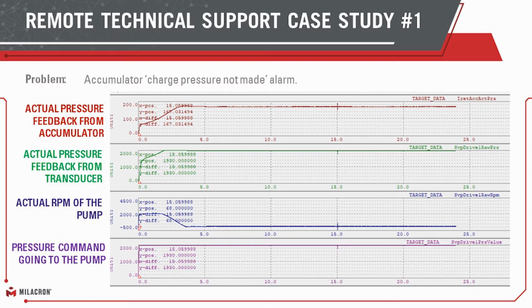Here you see an example of some of the things our technicians have actually done using this system to help our customers. They were able to look at four specific things that helped us narrow down and get a handle on this issue. We looked at the actual feedback from the accumulator itself, a transducer in the system, and the drive feedback of what we're asking the accumulators to do. We were able to look at the pump that charges the accumulators and make sure it's getting the proper command and output, and relate this back to what it's being asked to do to see if it can meet those requirements.